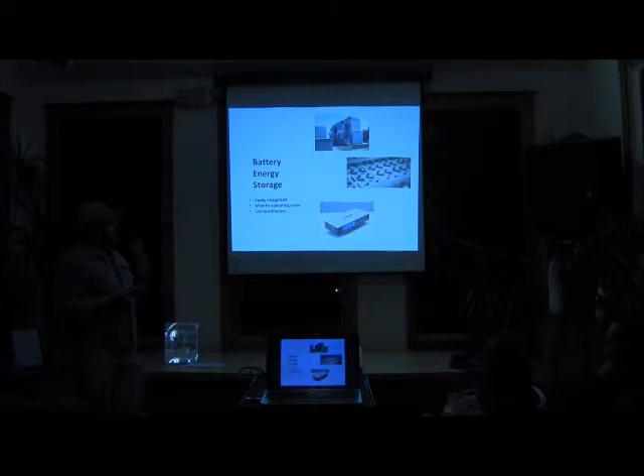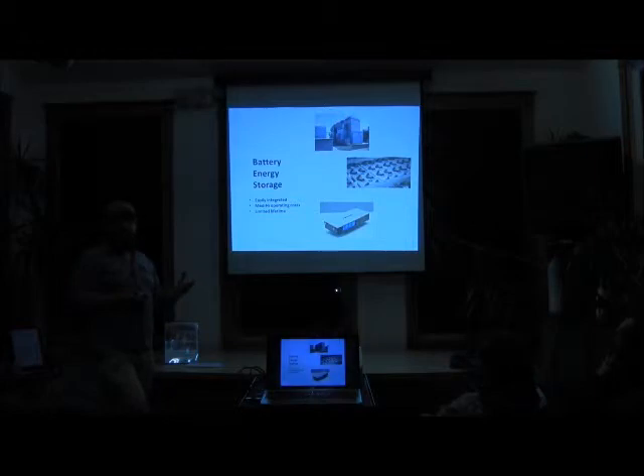The problem is really the lifetime. Those are like lead acid units, so you get maybe 10 to 15 years before you have to replace the batteries. And especially on our system where there's such big changes, it would cycle a lot. So we'd probably get even less time out of it. You could go with a lithium ion battery, but then your cost is gonna be about 3 times what it is for the lead acid system, so.